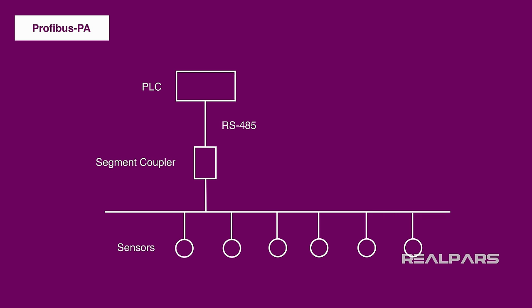The good news is though, that most PLCs do have a Profibus DP port. So by utilizing this segment coupler or converter, you can use Profibus PA in the old systems as well. By doing this, you actually end up with a Profibus DP before the converter and a Profibus PA after.